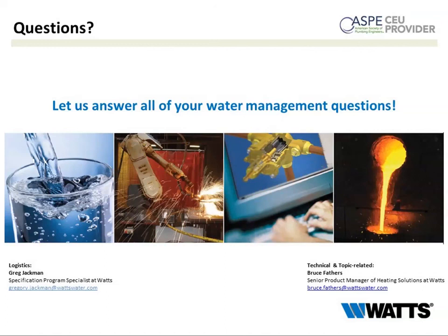Next question that came through: if the sanitation mode is standard, would special precautions be required for the network downstream, plumbing fixtures, valves, etc.? Most facilities, if they're using sanitization, are going to have a protocol in place to ensure there's supervision of everything downstream. In terms of the valves, you have to get the full hot water, because we talked earlier about limit stops needing to be installed and properly set. Those limit stops on all those valves are going to have to be removed so you can actually get full hot water.